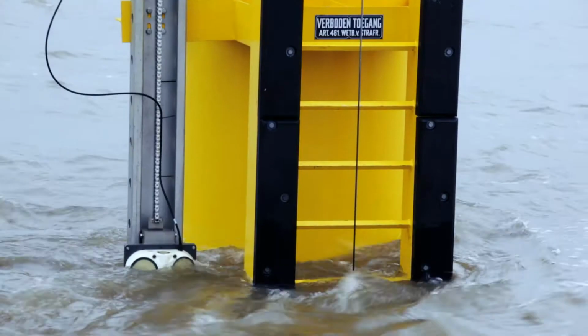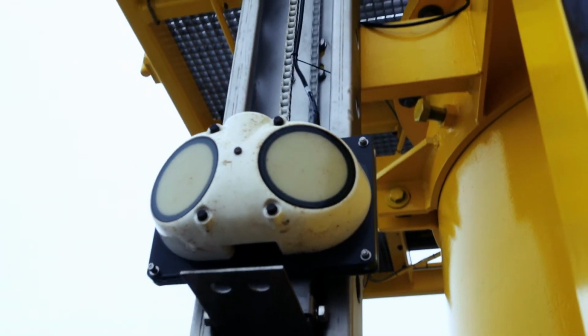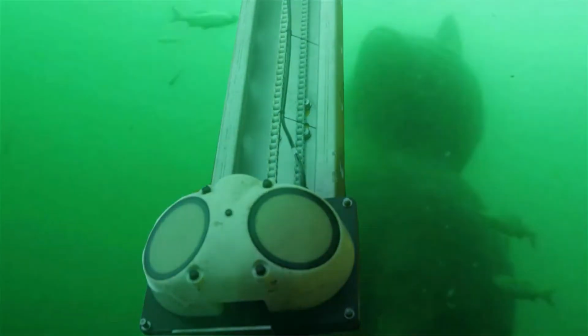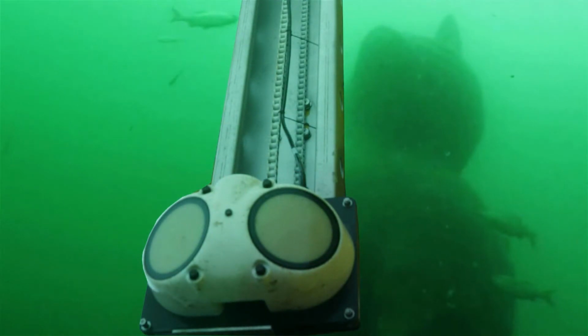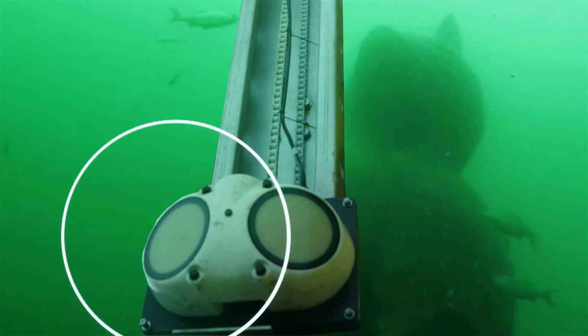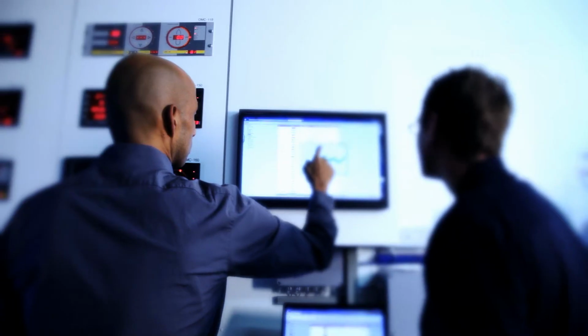To measure such a large variance in discharge is challenging. Observator decided to conduct the measurements with an acoustic instrument, a horizontal acoustic Doppler current profiler. It emits supersonic sound pulses through the water. The water reflects part of these pulses back to the instrument. From the Doppler shift of these reflections, the instrument calculates the speed of the water and, from that, the discharge in cubic meters per second.